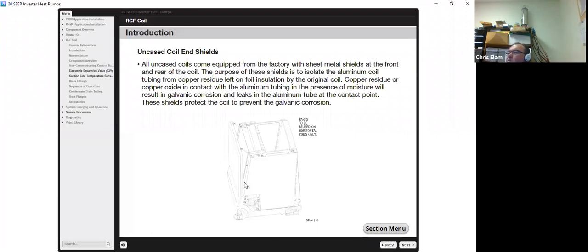Copper residue or copper oxide in contact with the aluminum tubing in the presence of moisture will result in galvanic corrosion and lead to leaks in the aluminum tube at the contact point. These shields are to protect the coil from galvanic corrosion.